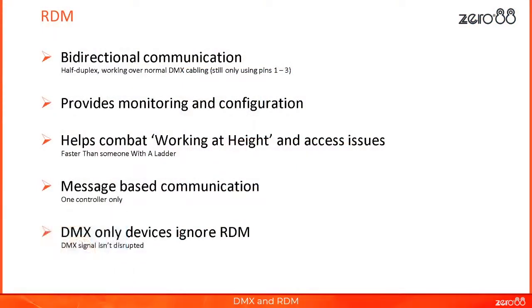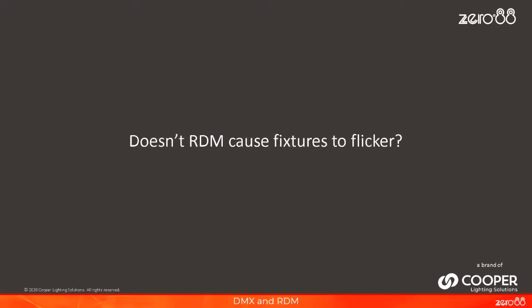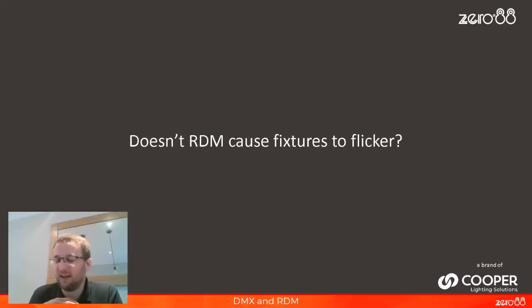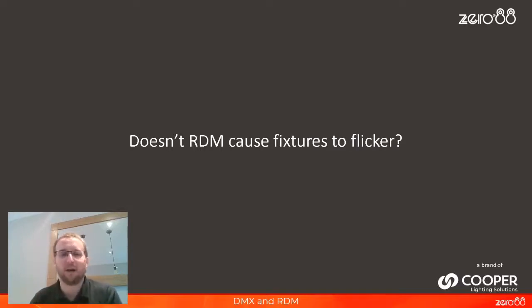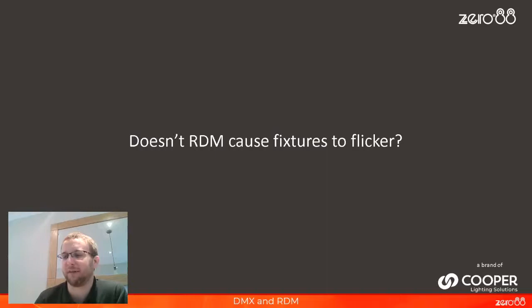DMX-only devices ignore RDM and the DMX signal isn't disrupted. This might lead to the question: if DMX-only devices ignore RDM, doesn't an RDM device cause flicker? This is a common assumption in the industry. RDM would never have been released if it caused your lights to flicker — so that is not in itself the problem. At a basic level, it can be true that turning on RDM causes lights to flicker, so let's investigate what's going on.